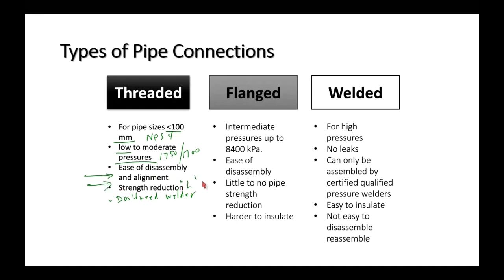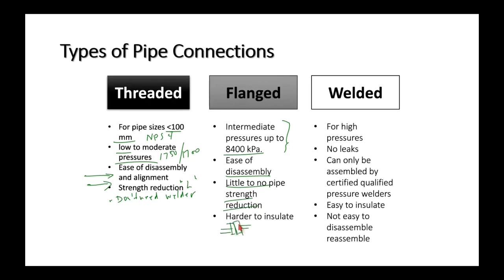Flanged connections are used for more intermediate pressures — up to about 8400 kPa. You can still disassemble and reassemble. There's little to no pipe strength reduction, but insulation becomes difficult around flanges — you need boxes around them.